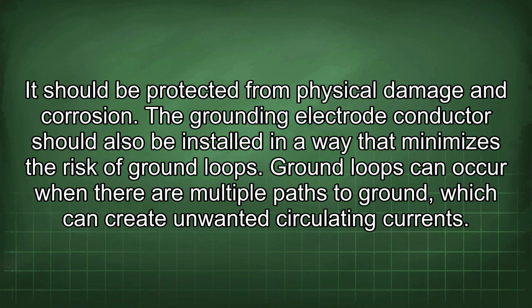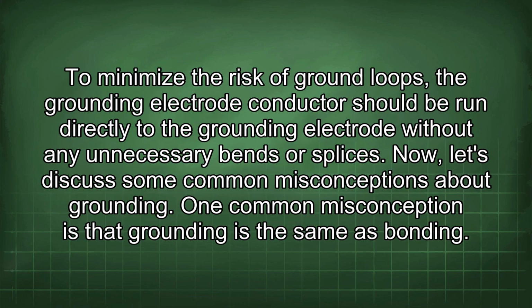The grounding electrode conductor should also be installed in a way that minimizes the risk of ground loops. Ground loops can occur when there are multiple paths to ground, which can create unwanted circulating currents. To minimize the risk of ground loops, the grounding electrode conductor should be run directly to the grounding electrode without any unnecessary bends or splices.